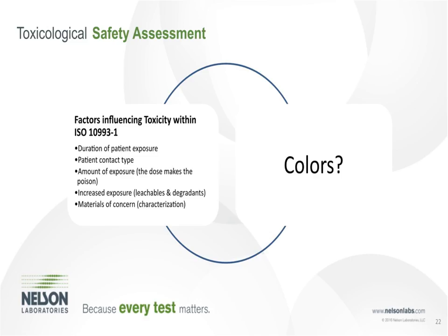If you have a colorant in your device that contacts the patient, especially if that device is more than just short-term contact, we have to have a specific section on that colorant. We have to do some kind of chemical leachability analysis on that colorant. We have to have a tox assessment done on the components of those colorants. You have to get that information from the colorant supplier, which is sometimes easier said than done.